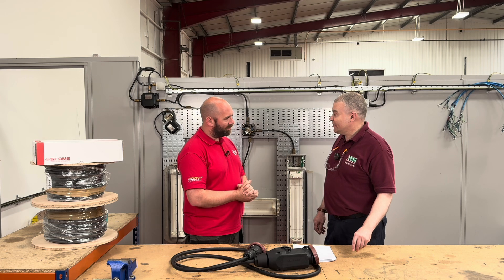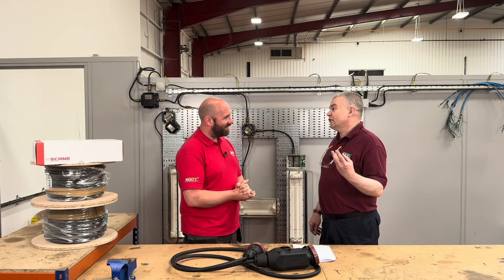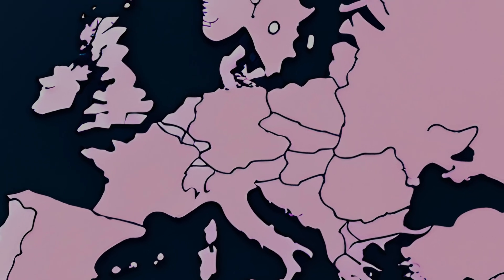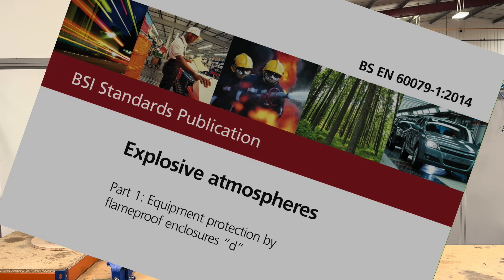It says it's ATEX rated, but what even is that? So ATEX stands for 'atmosphères explosibles' — it's the French term. They created a directive in 1994 stating that all equipment for hazardous areas must be the same so it could be sold throughout Europe. We've got British Standard 7671, and CENELEC which is the harmonised standard as well. This will be rated under CENELEC but also under British Standard 60079.